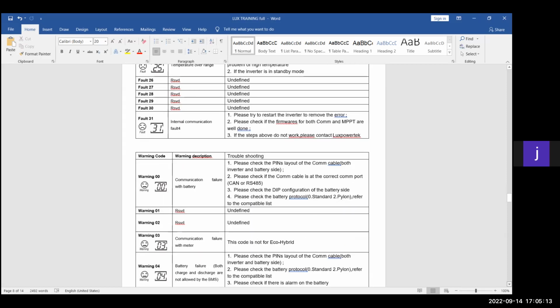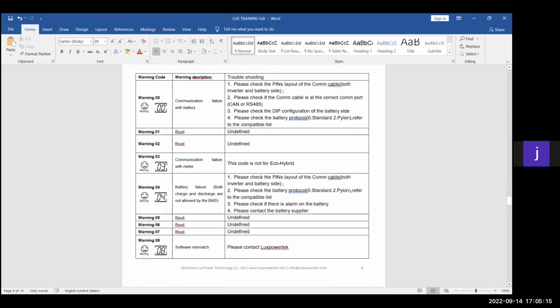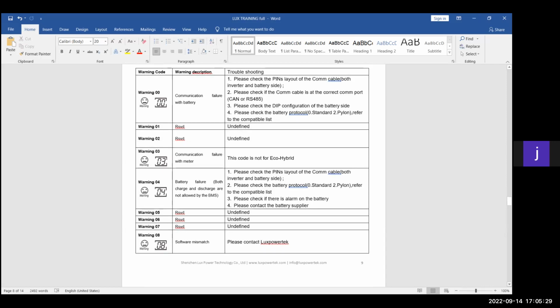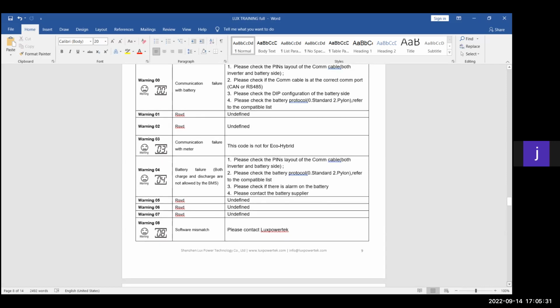From here on, you have your warning codes. 00 is one that you will have a lot. That's communication failure with battery. So just check your battery protocol, and it's very important to see if your battery is compatible with the inverter.